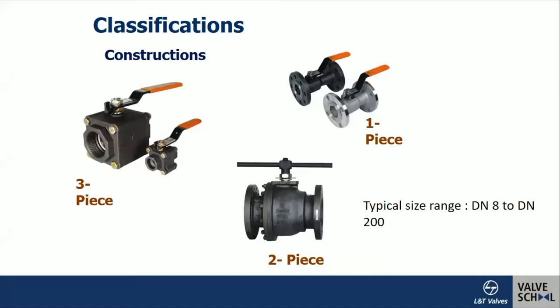Single-piece construction is the most prominent construction, having minimum leakage paths. It is good for gas applications because it has no potential leakage path other than the joint between the pipeline flange and the body flange. Two-piece construction has one body with an integral flange and another connector bolted together.